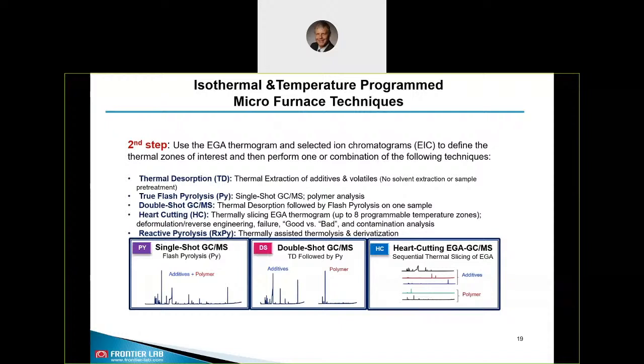Based on your EGA-MS result, you may select the best technique to answer your analytical questions. Maybe you only need thermal desorption — thermal extraction of light volatiles. Or you perform a true flash pyrolysis, also called single-shot GCMS for polymers. Or you can combine methods — double-shot analysis, which is thermal desorption followed by flash pyrolysis on one sample. Or you can even perform heart cutting, which is thermal slicing of the thermogram, for deformulation, reverse engineering, or failure analysis. Last but not least, you can also perform reactive pyrolysis using a derivatization agent like TMAH for example.